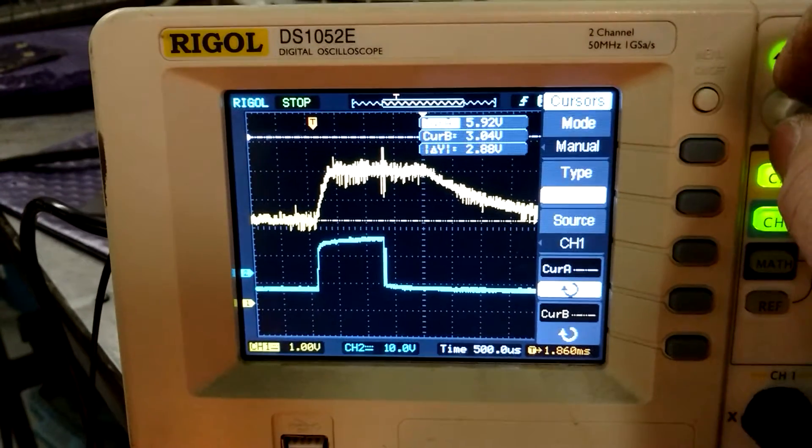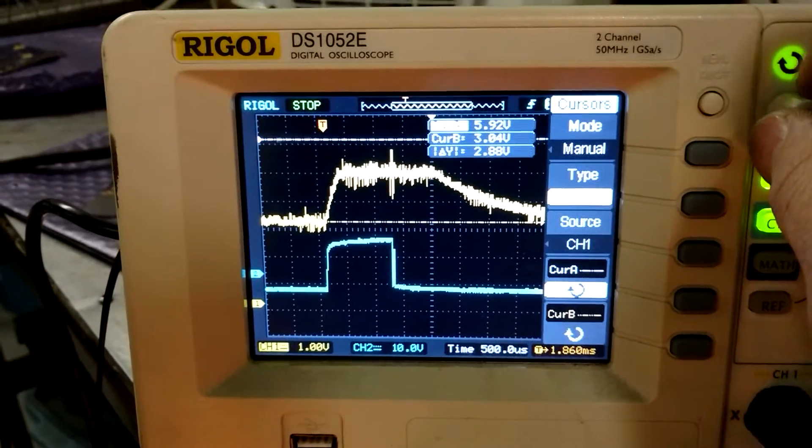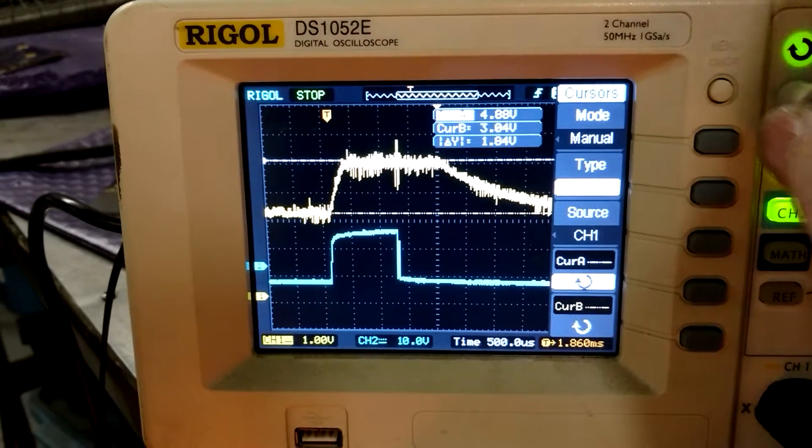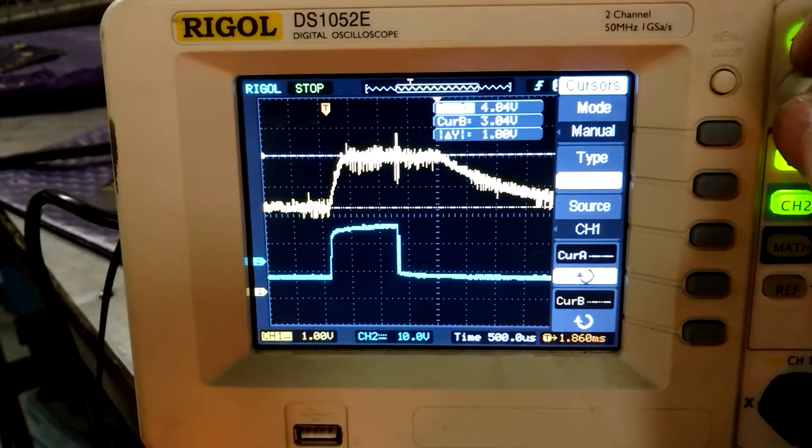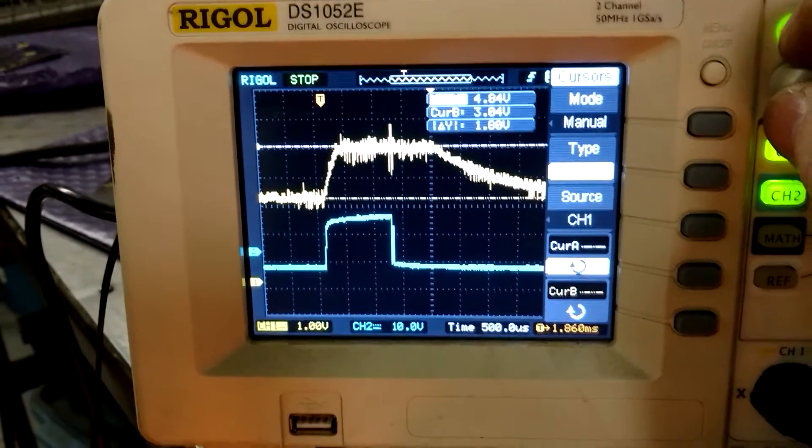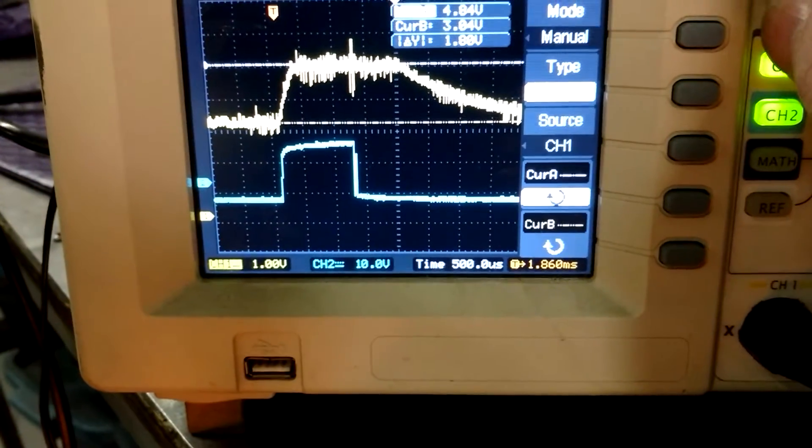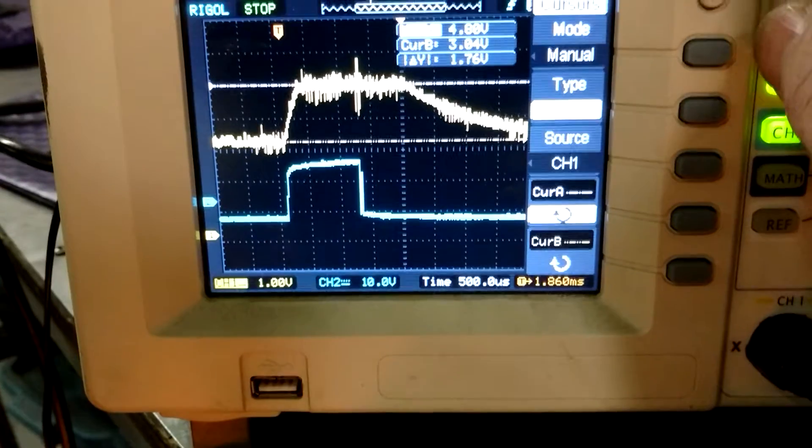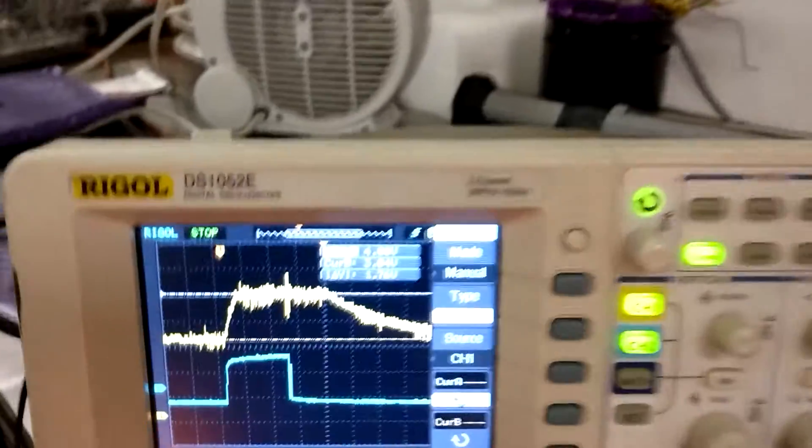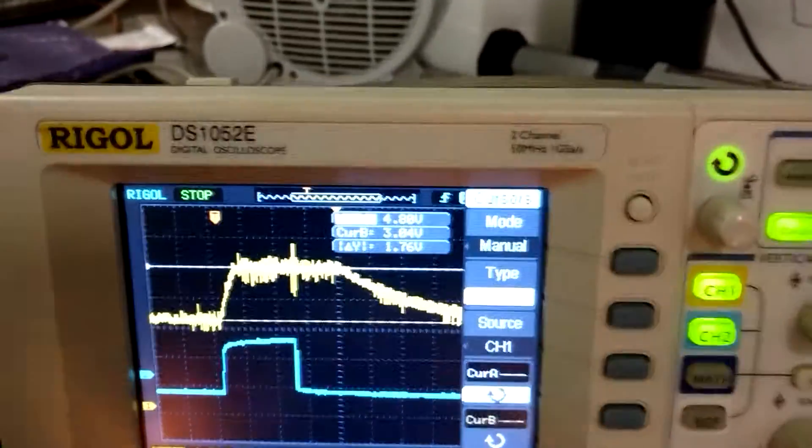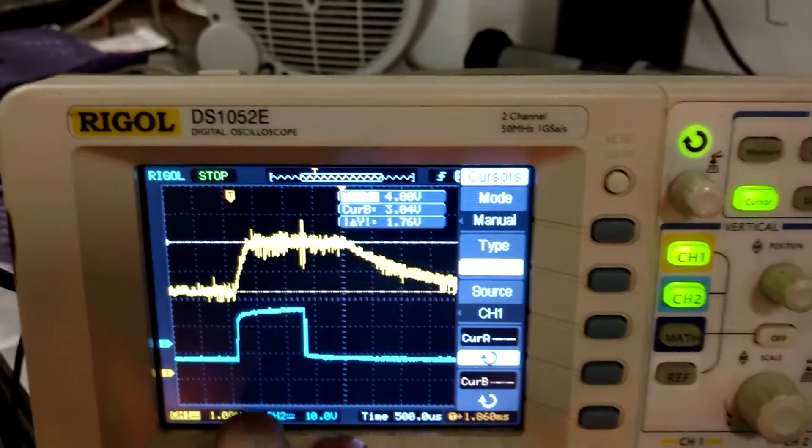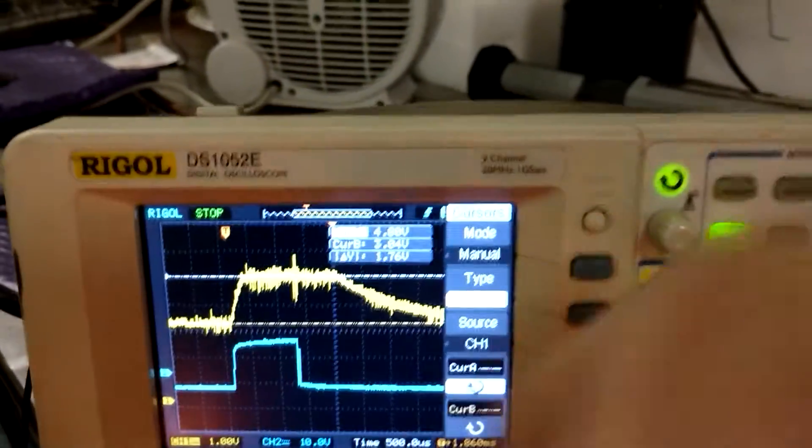But it's safe to say we're definitely, like this number right here, if you were to look at that, somewhere in the middle there, we're right around the 1.76, which with that 1.748 millivolts per amp, that's just a shy bit above 1,000 amps.